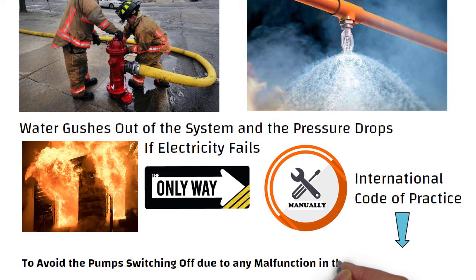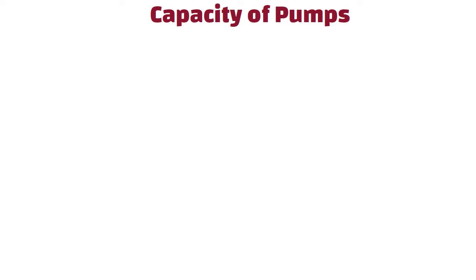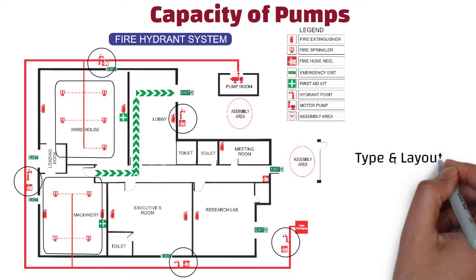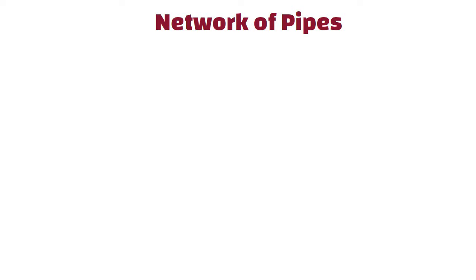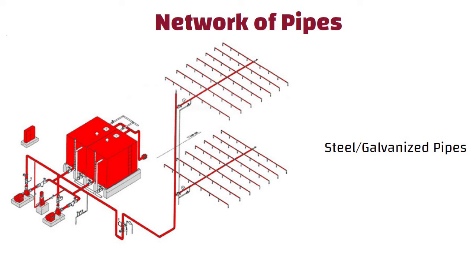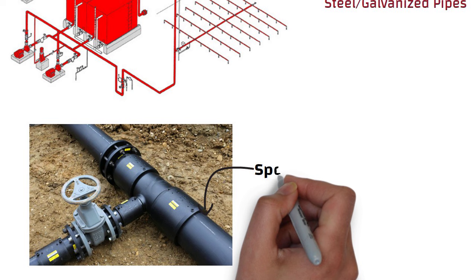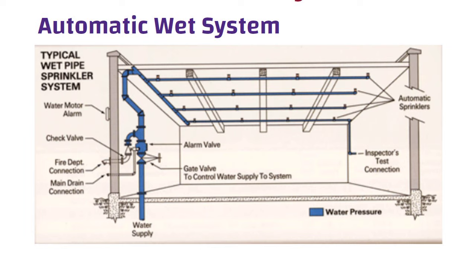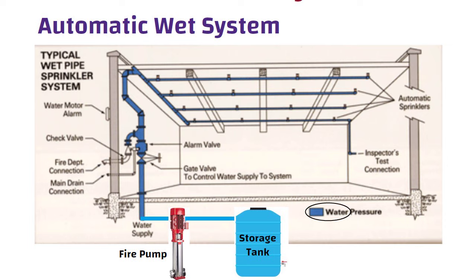The capacity of a pump is decided by considering factors such as the area covered by hydrants, standpipes, and sprinklers, and the type and layout of the building. The distribution system consists of steel or galvanized steel pipes that are painted red. When running underground, they are wrapped with a special coating that prevents corrosion and protects the pipe. There are basically two types of distribution systems: automatic wet systems and automatic dry systems. Automatic wet systems are the network of pipes filled with water connected to the pumps and storage tanks.